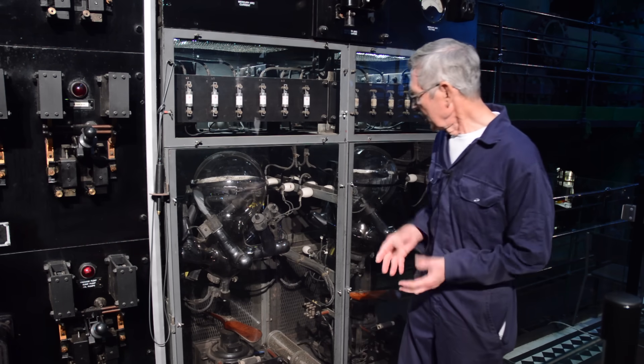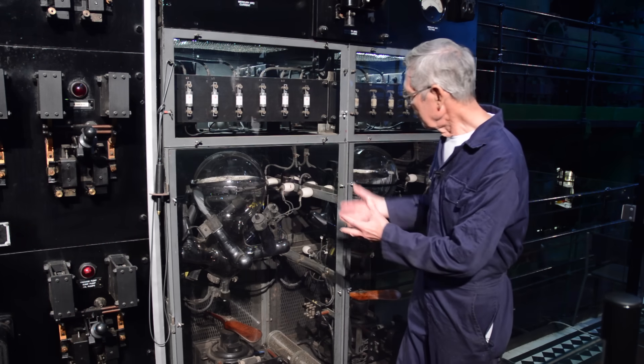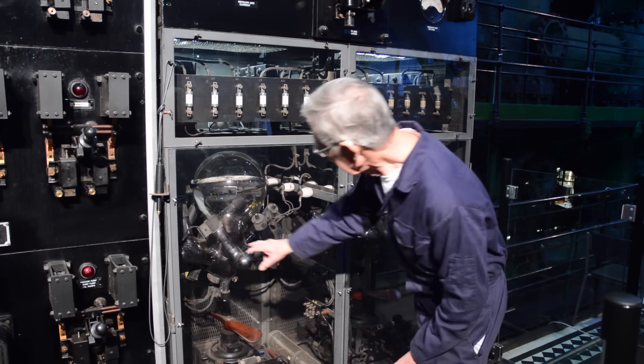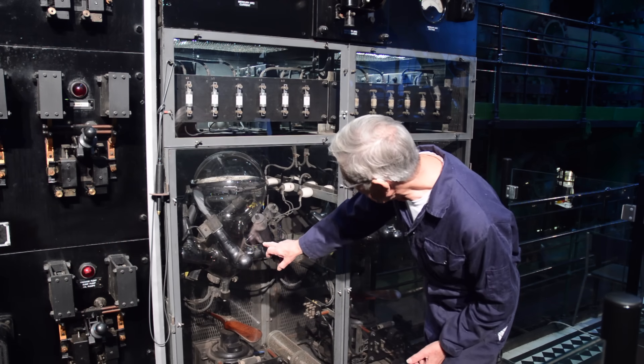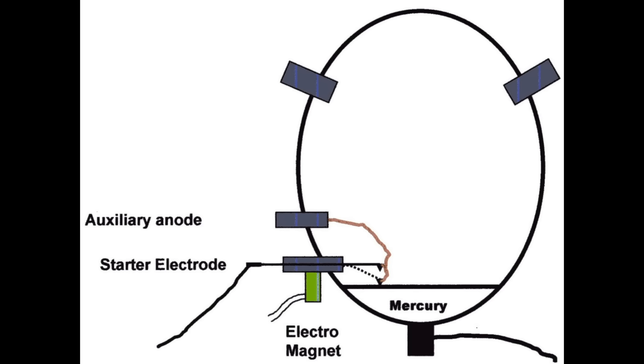Now to start a rectifier, you need an arc. And as it's a totally enclosed glass envelope, what you have is a spring wire from a small arm which is just out of sight, which has an electromagnet under it. When we start the rectifier, the electromagnet pulls the wire into the mercury pool. That shorts the electromagnet out, which releases the wire and creates a spark, which is then picked up by two small anodes at the back to keep the arc flowing.